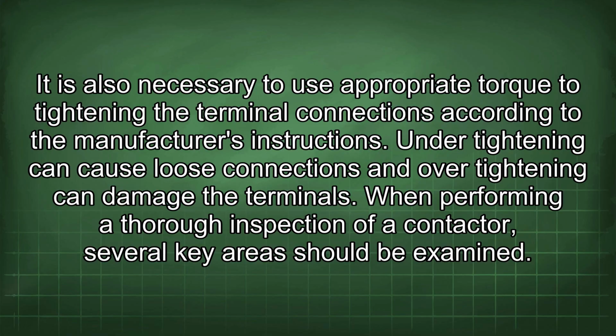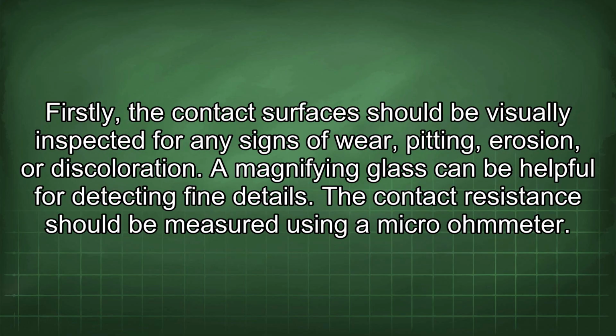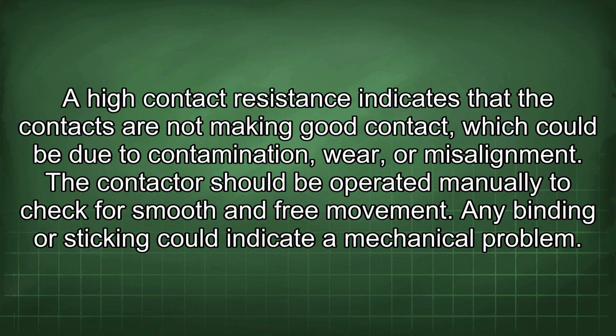When performing a thorough inspection of a contactor, several key areas should be examined. Firstly, the contact surfaces should be visually inspected for any signs of wear, pitting, erosion, or discoloration. A magnifying glass can be helpful for detecting fine details. The contact resistance should be measured using a micro-ohmmeter. A high contact resistance indicates that the contacts are not making good contact, which could be due to contamination, wear, or misalignment. The contactor should be operated manually to check for smooth and free movement. Any binding or sticking could indicate a mechanical problem.